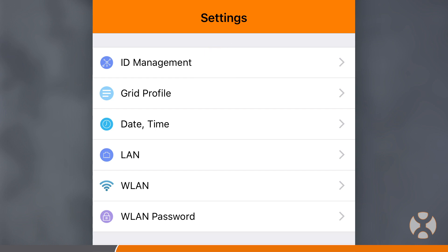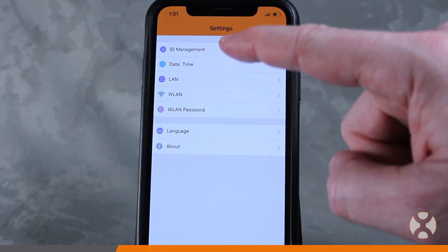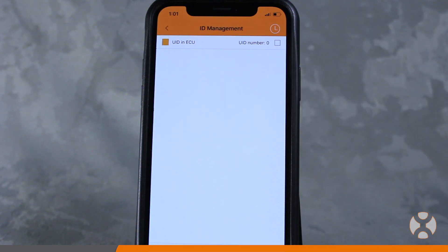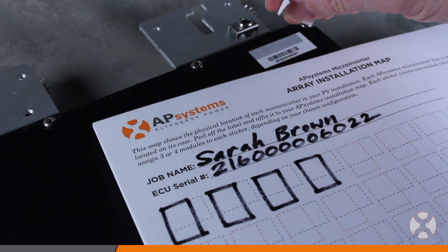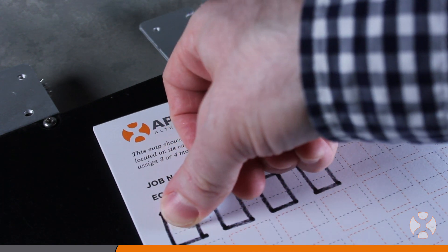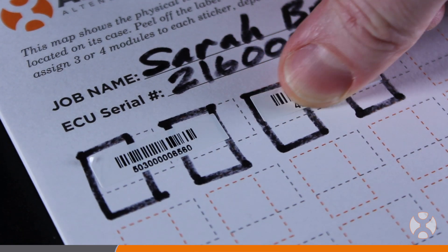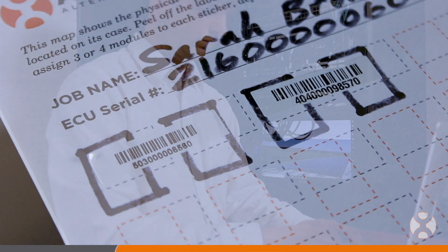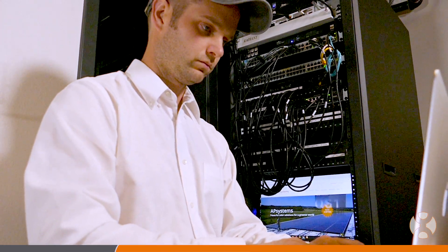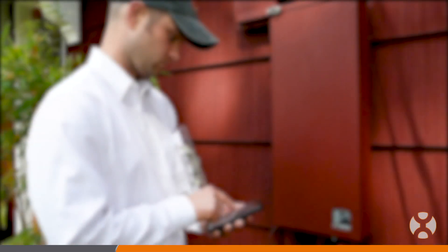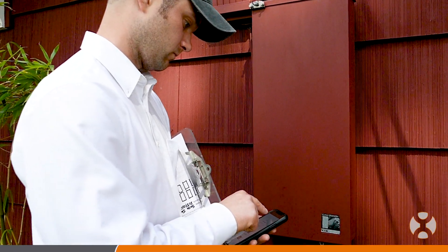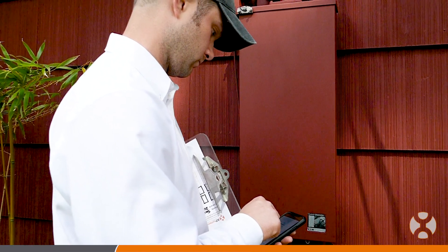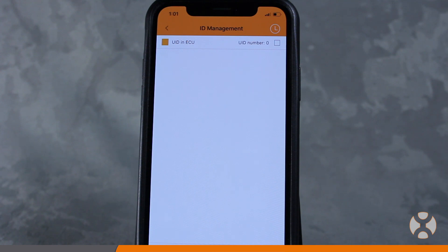The app will first sync with the ECU-R to determine the UIDs that have already been entered into the ECU. Many installers choose to pre-configure their ECUs with site-specific inverter UIDs prior to leaving the job site in order to save time during the ECU setup. If the app automatically finds all the inverters present in the array, the ECU is fully loaded with all the necessary UIDs and no syncing is required. If all the inverter UIDs do not appear, you may have to scan or manually enter them before syncing with the ECU.